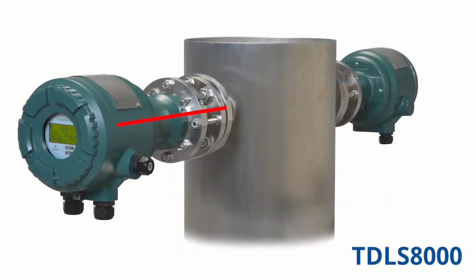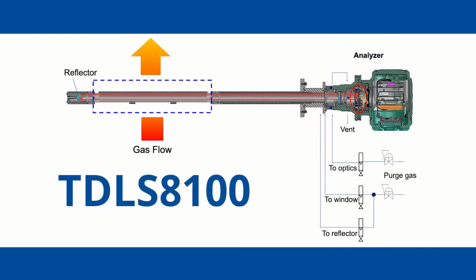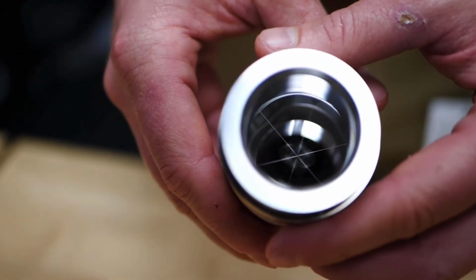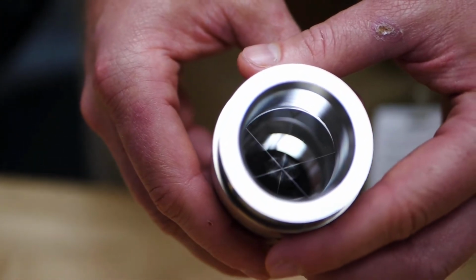Normal traditional TDLS units like our TDLS8000 will have a transmission end which shoots a laser across the process to the receiving end. The light lost at the receiving end correlates to absorption by the analyte of interest. The TDLS8100, however, operates by having the laser and detector mounted to the same process flange, still providing an in-situ measurement to avoid sample transport time delays introduced by extractive analyzers. The probe body has openings so that process gas can enter the measurement path. The laser is transmitted from the head to a retroreflector assembly, then bounced back to the detector also residing in the head of the analyzer.